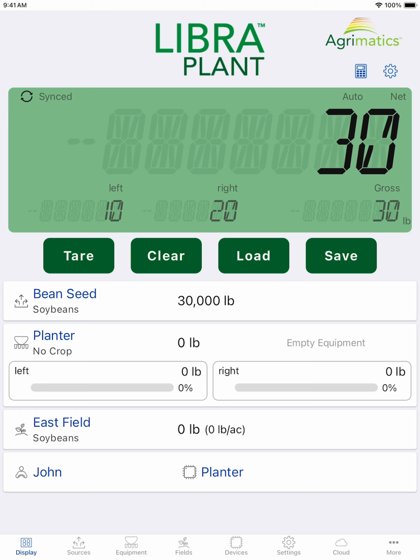Otherwise, if they're, for example, half as much as you thought they were, or should be, you're going to want to double that rated capacity. If it's twice as much, you're going to want to halve that rated capacity, or do any other kind of math that you have to do to make it work out. Once you have that number working out, you can move on to calibration.